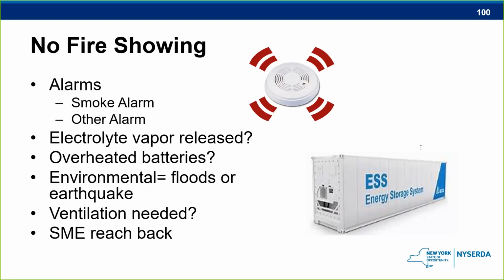Another thing that Jennifer said is that during lithium ion, this type of enclosure here, you don't need a ventilation. But I'm going to ask you, let's say there is a flammable cocktail in there where the cell heated up and all this gas came in and now it's stored inside there. How do you get it out when there's no ventilation? And this is what they saw in Arizona. They weren't able to get out any gases, but when they opened up a door that was part of the structure itself, the gases started coming out. Now, was it too rich to burn at that particular time? We don't know. There's still some forensics on it, so I don't want to talk too much about it, but I can tell you what I know at this particular point.